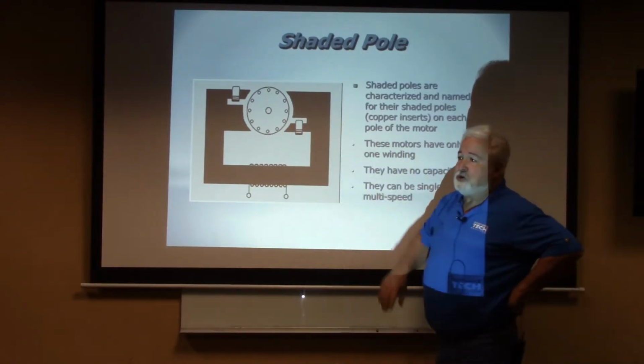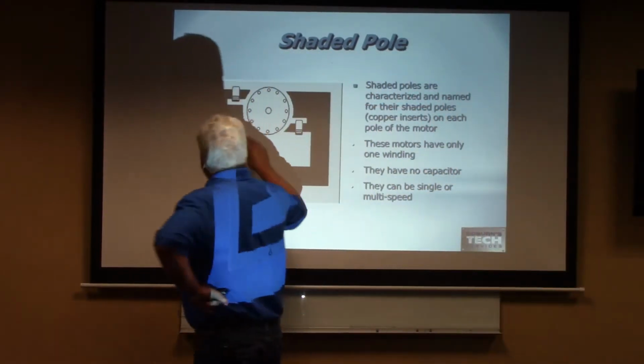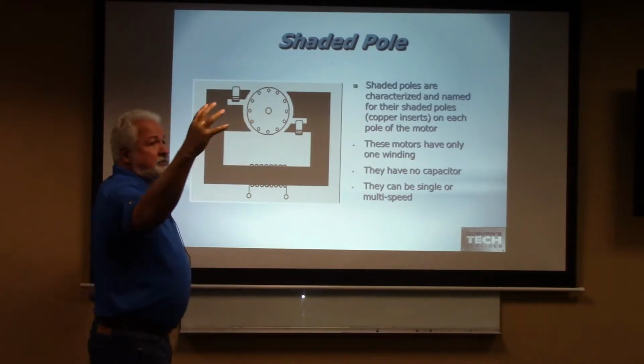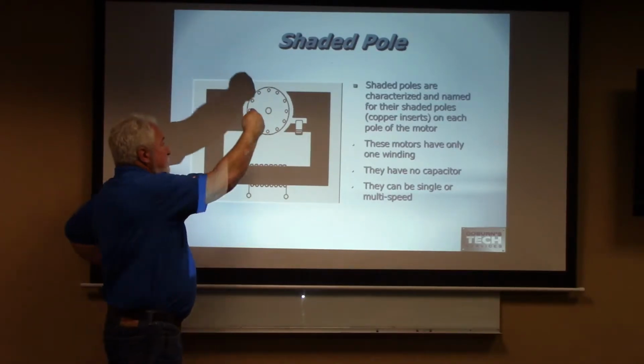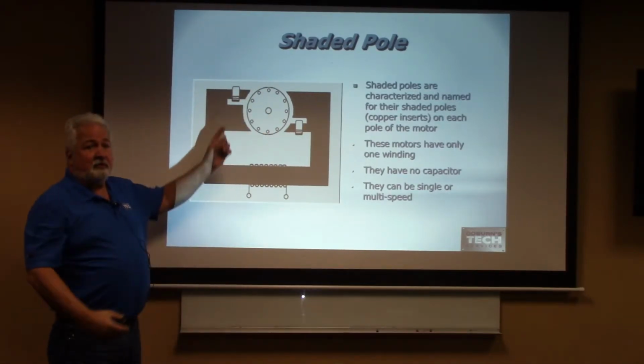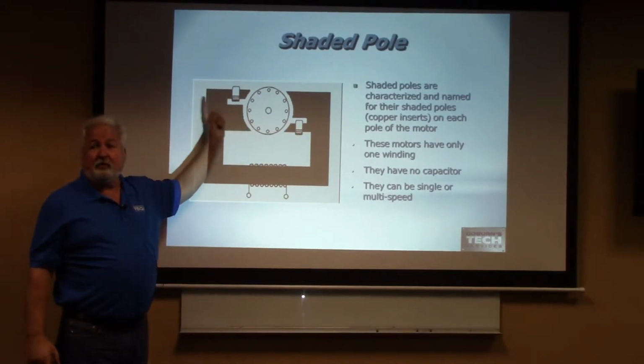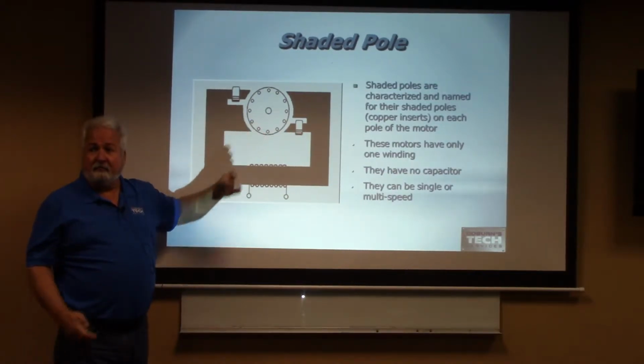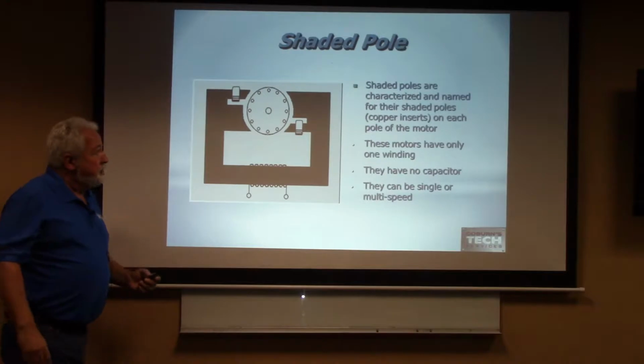And if you're going to change the direction on a shaded pole motor, you would take the stator out, flip it around, and shove it right back in again. Because the only thing that gives it direction is the poles themselves, the shaded poles. Good? Good. Shaded poles.